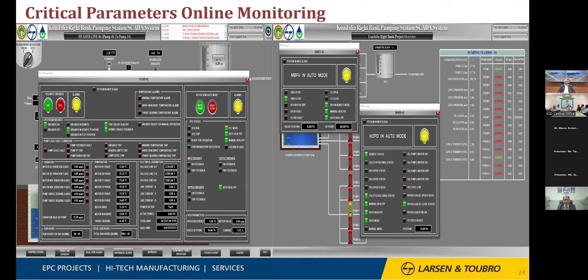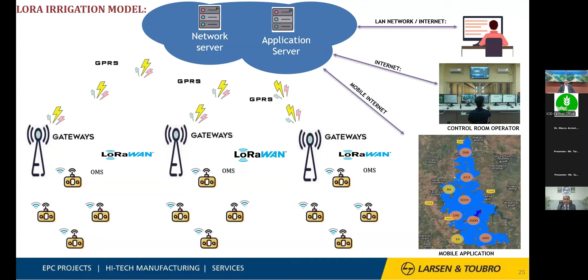Then this is the communication. Communication is very important because in the field we have to control a distribution network of 14,000 kilometers, so it cannot be controlled without communication. We cannot have people at every field location to give us alerts. So how does it communicate? The OMS, AMS or RMS communicate to the LoRa gateways, which have been installed at suitable points in the area. Then the LoRa gateways communicate to the cloud server through GPRS, meaning GSM based. The cloud server can be accessed through the internet, through the mobile app, or through the regular LAN network at our control room. So we get all the live data for the distribution network at the control center. With the set username and password, we can access it from anywhere in the world where internet is available. The complete system is designed like that.